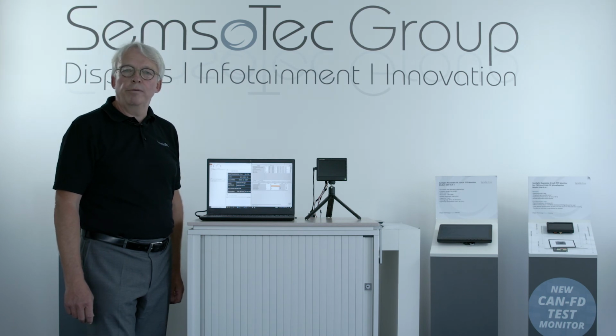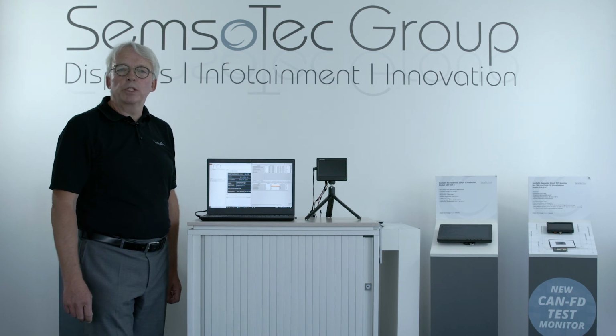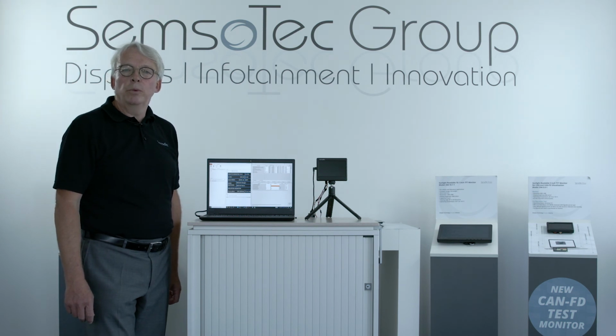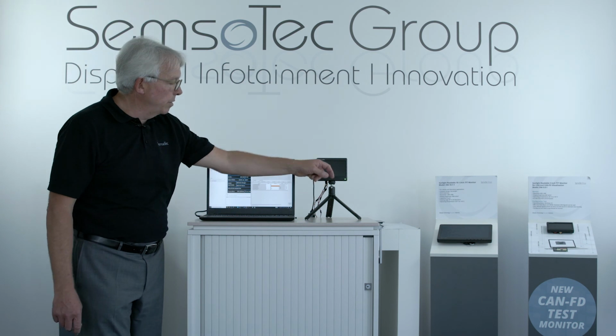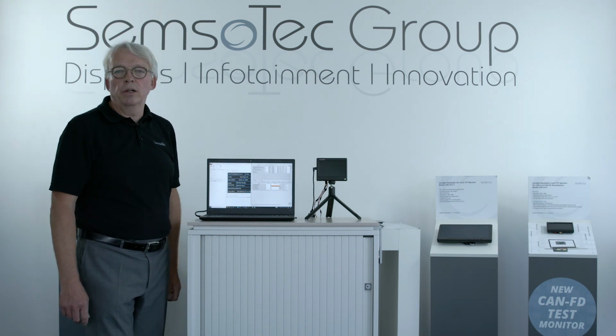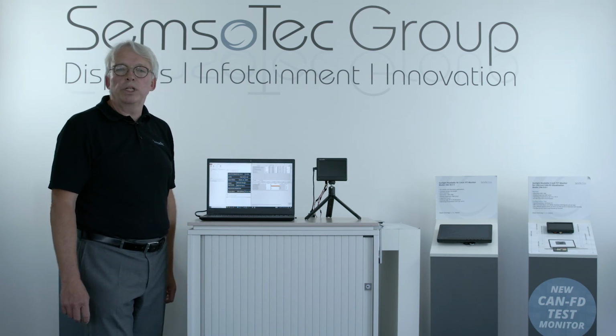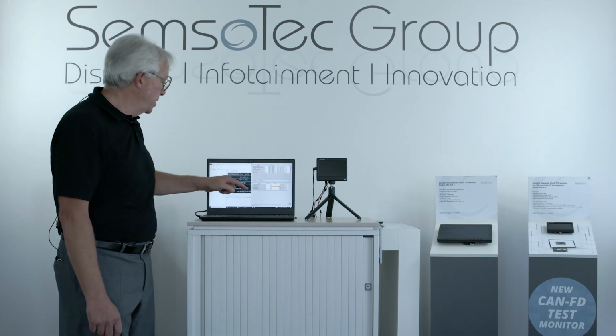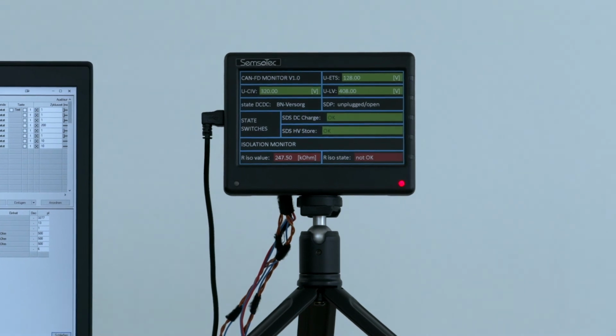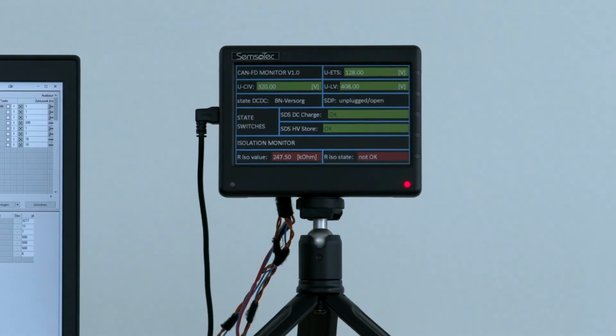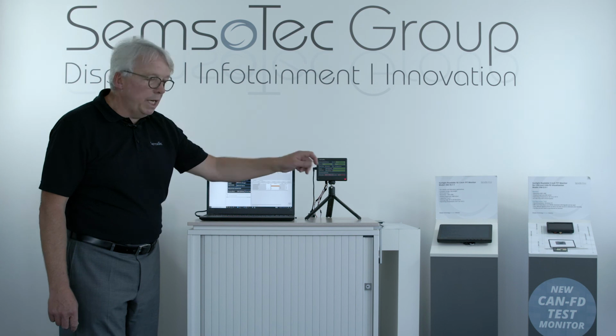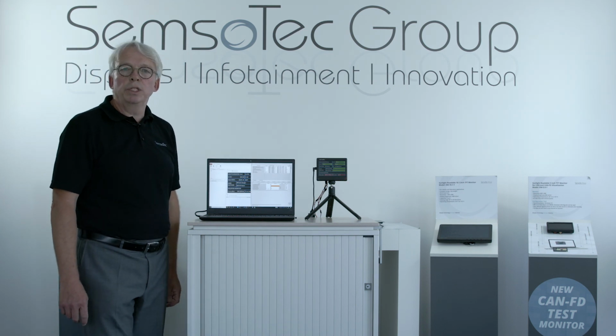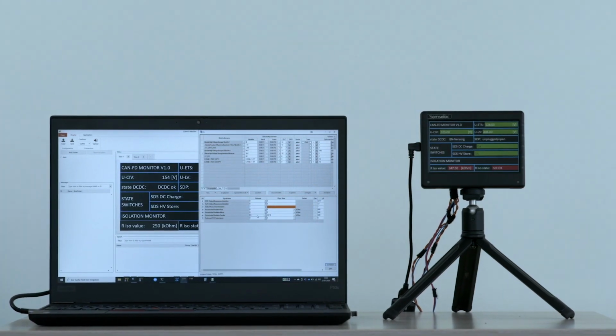without disturbing the driver. We've set up a simulation to show the possibilities for alarms, which include the LED on the front of the monitor, an acoustic signal, and waking the monitor up from the sleep mode. I'll start the simulation from the PC. We saw the red LED, we heard the acoustic signal, and the monitor was woken from the sleep mode.